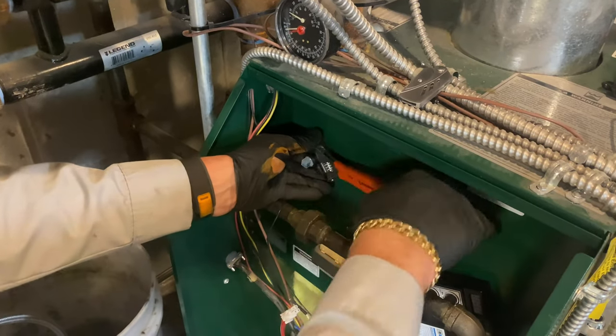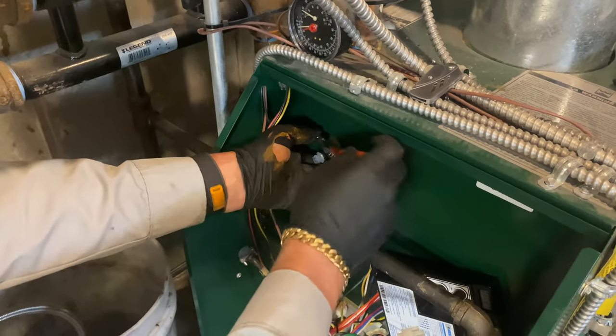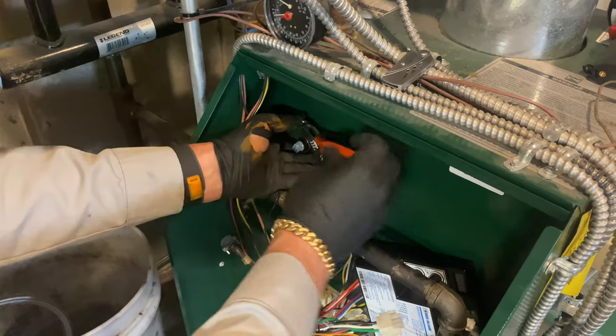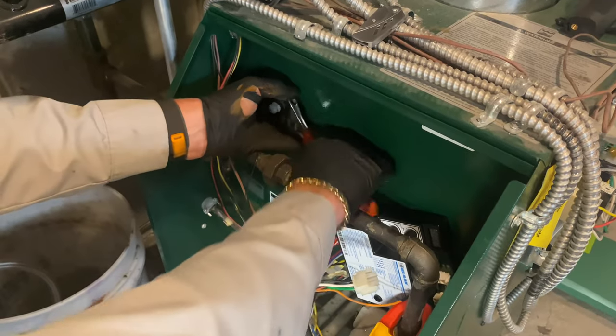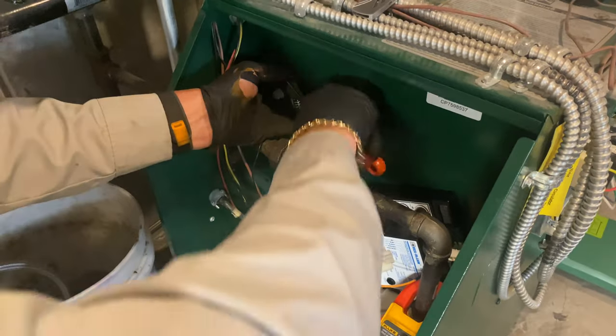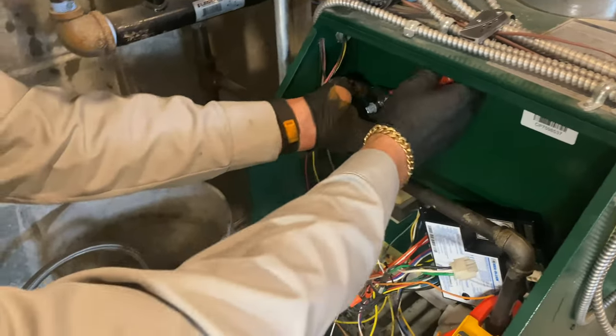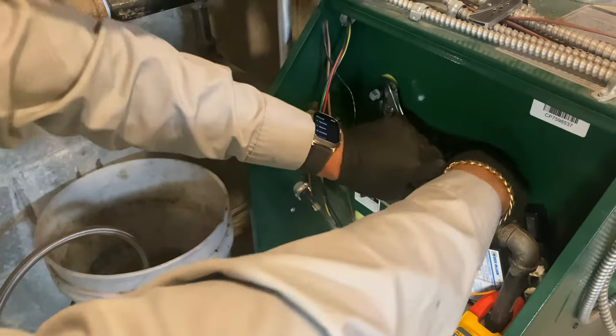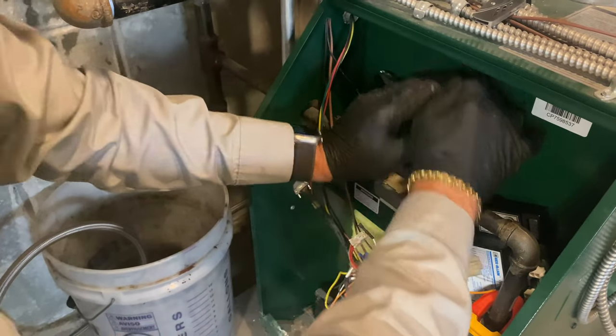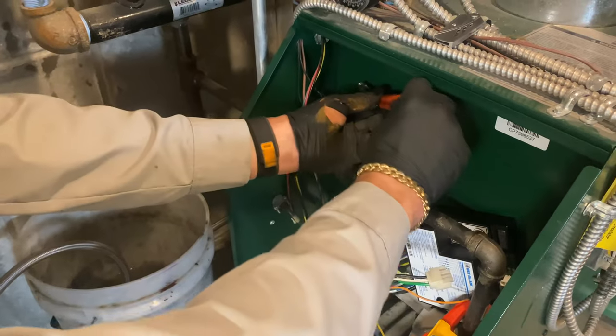Okay, remember, no Teflon tape. Yeah, it's called PTFE tape, that means the Blue Monster, any kind of tape that you wrap around the threads, is not to be used, because you will not get a sense from it if there's a low water condition. You may even get that error that the low water cutoff is a problem.